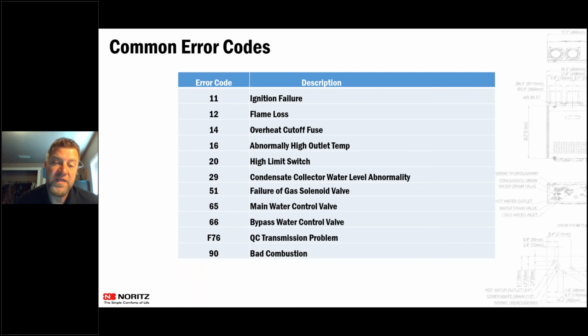So 29 is going to be your condensate collector water abnormality, which just means there's a little sensor in there that if the water level gets too high inside of that trap, it will set that 29 code off and shut down the unit so it doesn't back condensate up inside of that unit. That just means that there's a block inside of that condensate system somewhere from the trap internally down to the drain. A lot of times it could just be a whole bunch of buildup that's gotten blocked off in there. Best way to fix that is at the condensate collector: you can just dump water down the exhaust and it'll flush out the condensate line.